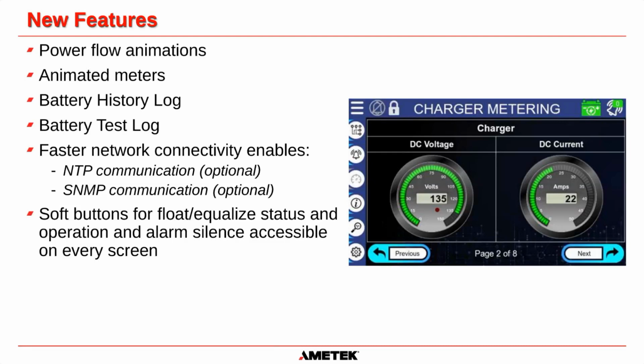We have faster network connectivity than we previously had, and due to this new network connectivity, we can do NTP communication, which is network time protocol. Once every hour, the system will go out to a server. You enter the IP address on the system, and it'll update its current time with the server. We also have built-in SNMP communication that we did not have in the previous versions. It's also an option, but we can select it very easily, and there's no extra hardware required.